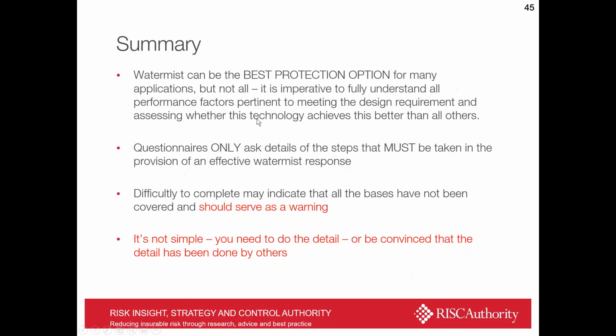So in summary, just really to close out, water mist can be the best protection option for many applications, but not all. It is imperative to fully understand all performance factors pertinent to meeting the design requirements and assessing whether the technology, what it can achieve, is better than all others. The questionnaires only ask questions that should be answerable by anyone competent to design and install a system. And really, if people are struggling to justify the system or to complete the questionnaire, that should serve as a warning to you.